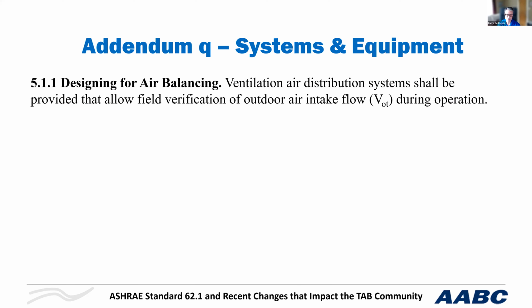Okay, well, that's good. So 50% or more of the time we have trouble adequately balancing the outside air, which is the case, and that's what we're going to talk about right now. One of these important changes, which you on the call would think is obvious, is not. This is an important change for the industry to ensure that designers and manufacturers provide suitable access to allow not only for good air profile, so that the balancer can get in there and actually do his job. Make sure that he's not bypassing the airflow or blocking the airflow as it's going in, and to make sure that we can actually set it. I mean, we're not miracle workers out here trying to set the flow rates. So it's important for all of us to impress on everybody that's responsible, whether it be the installers, the manufacturers, engineers, or designers, that this is in the standard and it's an important thing to follow.